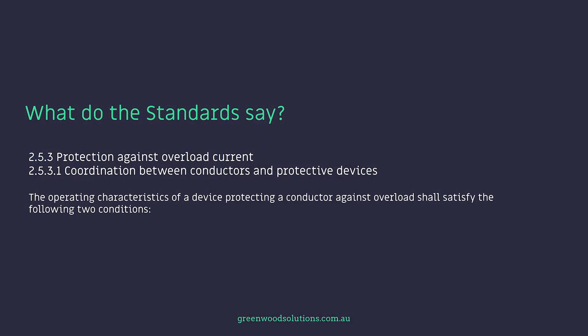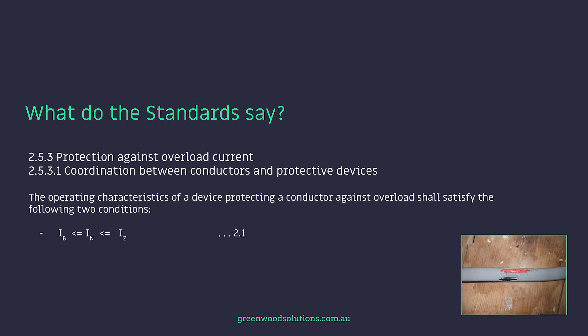Now the standards are very particular about what is required from the point of view of the protective device. Clause 2.5.3 — protection against overload current — AS3000 2018 version, and 2.5.3.1 coordination between conductors and protective devices. The operating characteristics of a device protecting a conductor against overload shall satisfy the following two conditions: IB ≤ IN ≤ IZ, and I2 ≤ 1.45 × IZ.